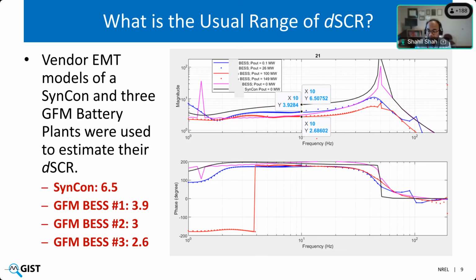Before we dive into different performance metrics and test methods for voltage source behavior, another thing I would like to point out is that if we compare this dynamic short circuit ratio provided by these different resources, the synchronous condenser is providing around 6.5, whereas for the grid forming BESS the gain ranges from 2.5 to 4.5. We have seen this behavior again and again: grid forming BESS does provide a good amount of dynamic grid strength support using this gain from Q by V scans or P by theta scans, but it is usually lower than what a synchronous condenser of the same capacity would provide.